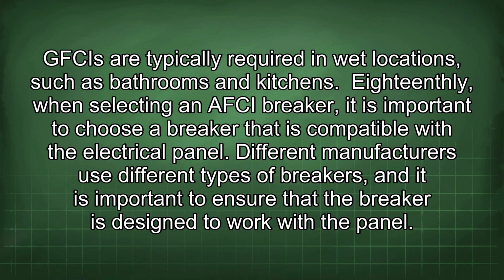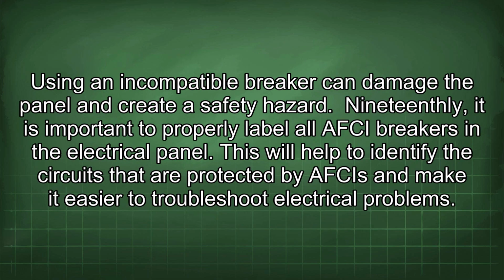18thly, when selecting an AFCI breaker, it is important to choose a breaker that is compatible with the electrical panel. Different manufacturers use different types of breakers, and it is important to ensure that the breaker is designed to work with the panel. Using an incompatible breaker can damage the panel and create a safety hazard.